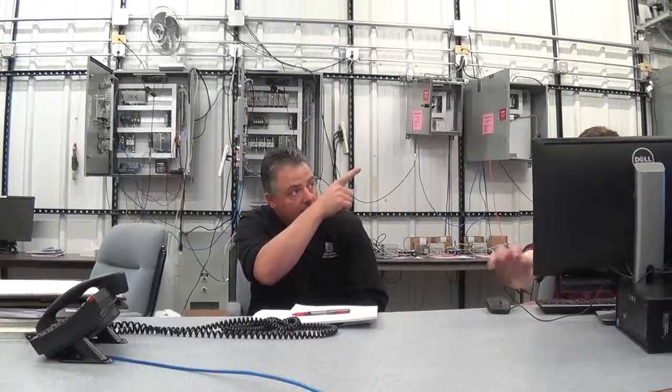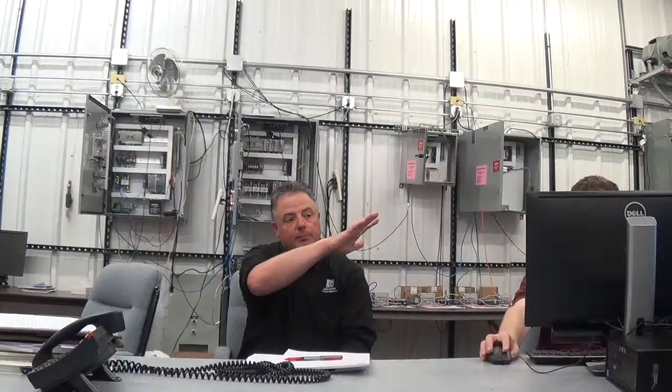But so, alarm comes in. If nobody's at the computer, nobody hits that acknowledge button. There's a delay right up the top, so it waits that delay to allow somebody to respond. So you put like 2 minutes in, or whatever time you want in there. If somebody's sitting at the computer, they can acknowledge it so it doesn't go out to the dialer. Because you guys have to realize, this computer is not going to be at a wastewater treatment plant. I know. I'm just saying it's probably never going to be acknowledged, depending on where it's located.